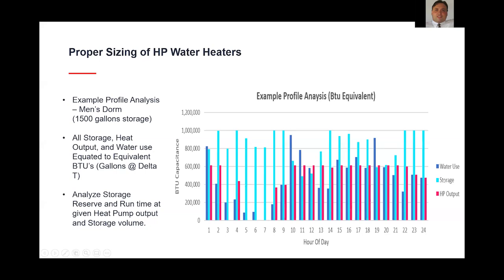And we had plenty of storage reserve. Storage is indicated by the blue. At no time did this ever get depleted. And you can see by the red output, that's your heat pump output. We've got, in this case, I think it was close to 14 to 15 hours a day, equivalent hours. Some of these are part load hours where that heat pump is running. So that would completely be valid in this scenario. We've got a heat pump that's running more than 10 hours a day. We've never depleted our storage. And again, you can play with this and iterate it through multiple iterations, trading off heat pump quantity, heat pump output versus storage.